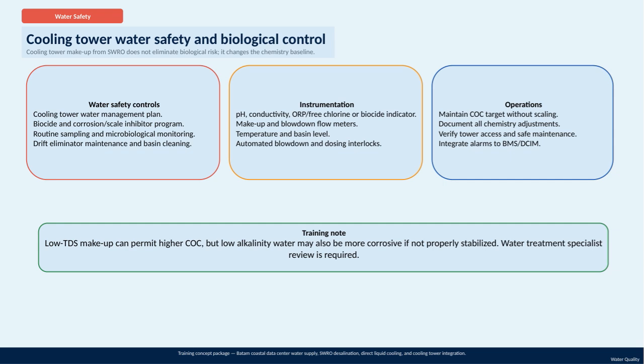While low total dissolved solids, or TDS, makeup water can allow higher cycles of concentration, low alkalinity water may be more corrosive if it's not properly stabilized. This means water treatment specialists must review and guide the process to avoid problems. This comprehensive approach ensures both safety and efficiency in cooling tower water management.